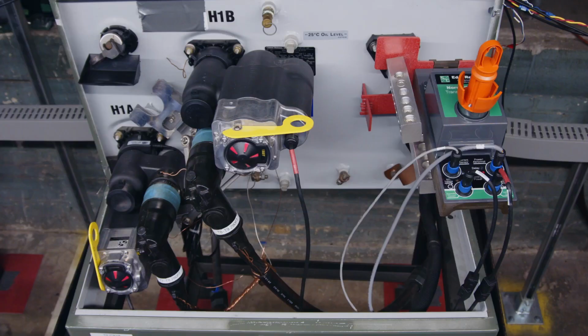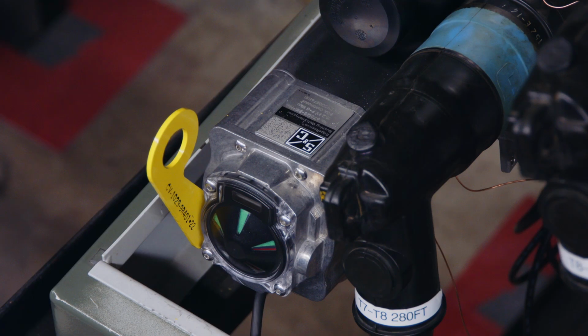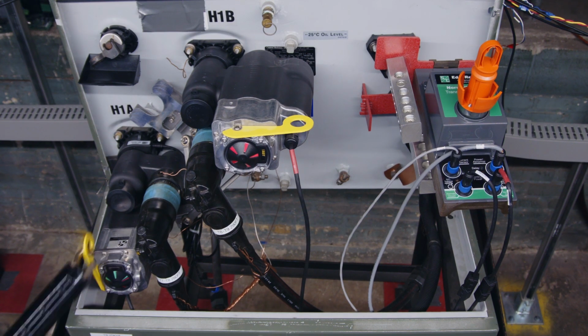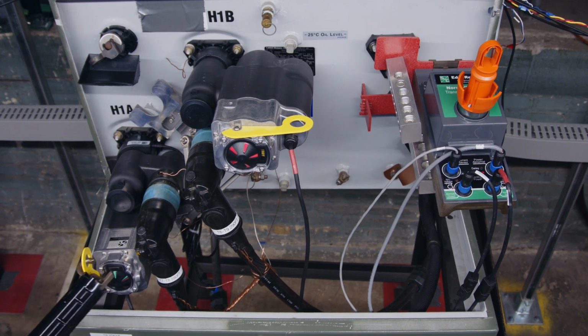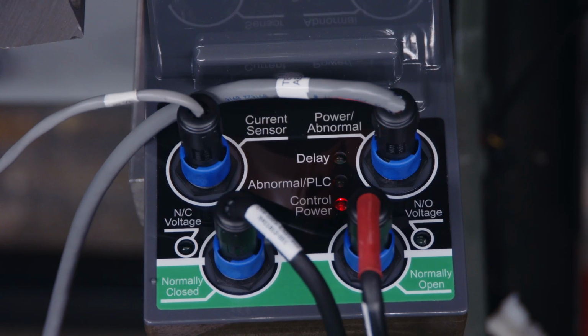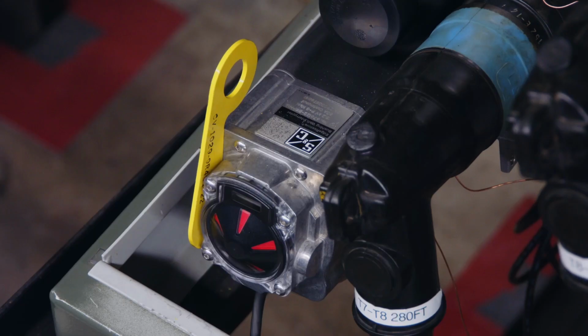Step 6. Open the H1A bushing well interrupter by pulling the yellow lever forward once. Step 7. Close the H1A bushing well interrupter by toggling the handle from the open, green, and locked position to the ready position 3 times, ending in the ready position. Step 8. Make sure the delay LED is blinking. It will blink 10 times and then the bushing well interrupter will close. Step 9. Make sure the indicator on the bushing well interrupter is in the closed and ready position.